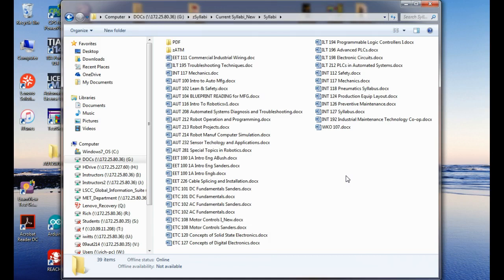Then we have interpreters, which compile on the fly. When you put your PLC on monitor and look at your ladder diagram — a high-level language — you're actually monitoring via a translator doing it on the fly. An interpreter does not create a machine language program; it does it on the fly. A compiler translates it completely. So when you upload from your PLC, the compiler takes a binary program and translates it into a ladder diagram for you to watch.